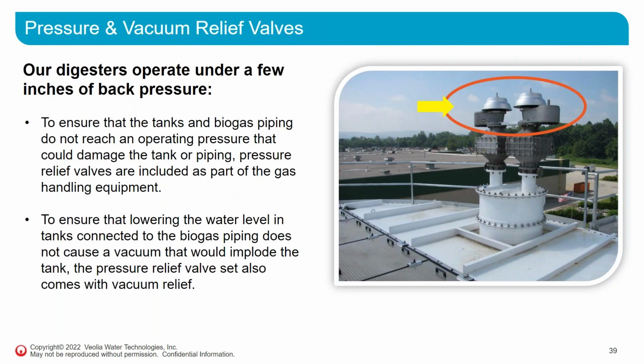So pressure and vacuum relief valves will be installed in the line and especially on the reactor tank. It ensures that any overpressure or vacuum situations are relieved through the valve so that the tank doesn't implode or rupture. You can see in the picture the top part of that is a pressure relief, and the part that sticks out on the side is the vacuum relief component. You need to make sure that you don't get birds' nests or other debris built up in there, because that could clog it.